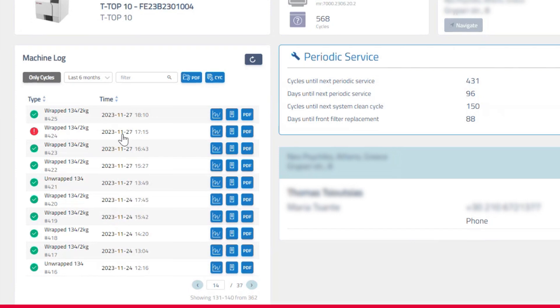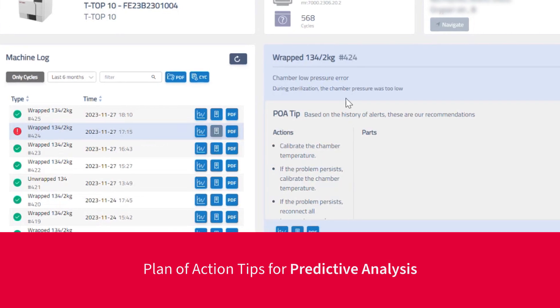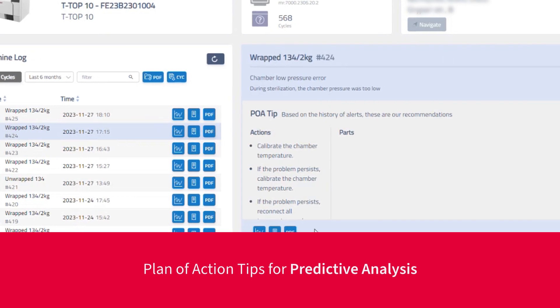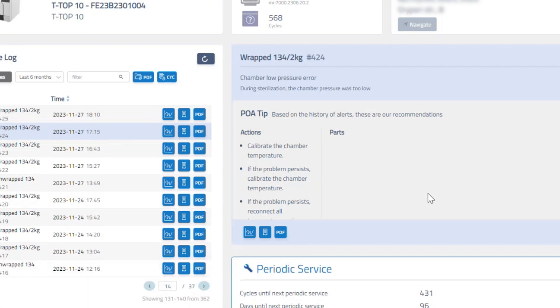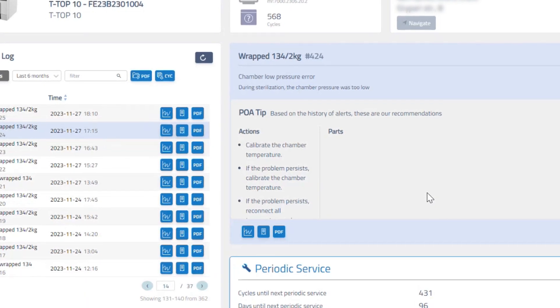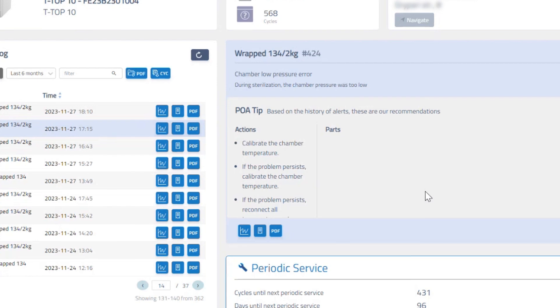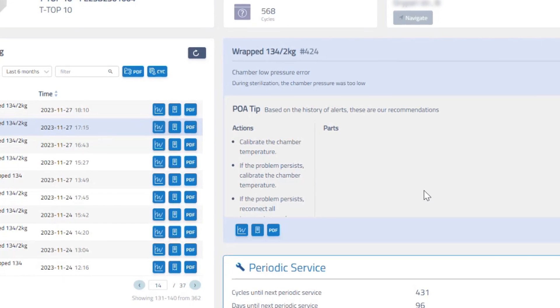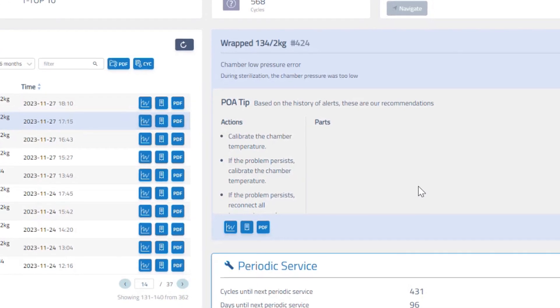Service providers will receive plan-of-action tips customized for that device based on past failure alerts and be able to receive alerts that indicate abnormal behavior in a successful cycle, allowing you to provide preventive solutions for your customers.